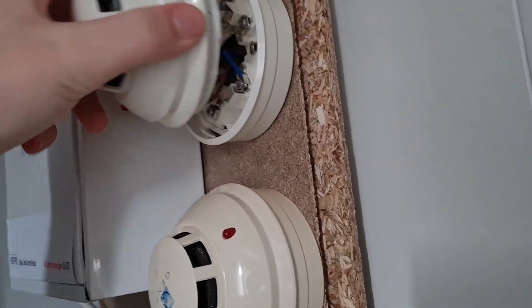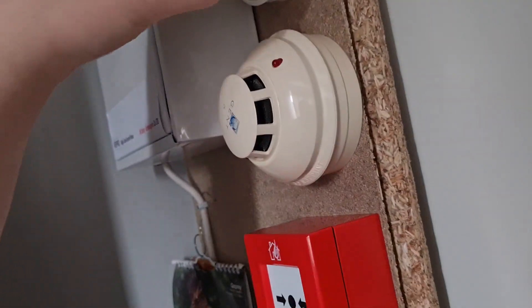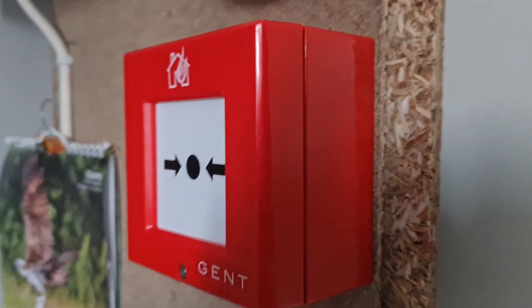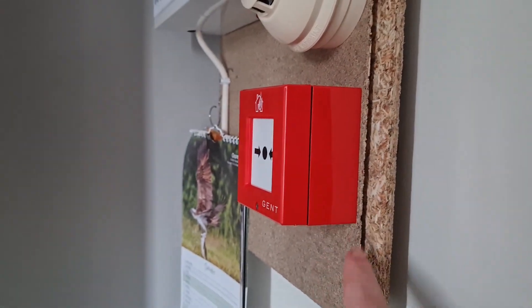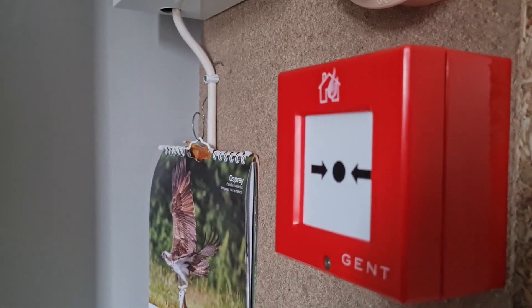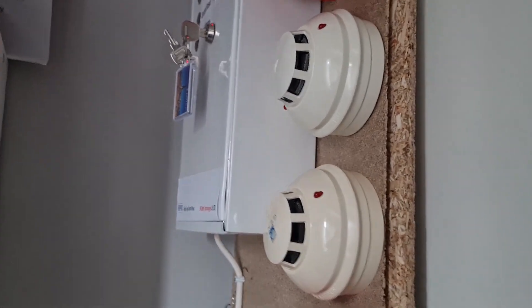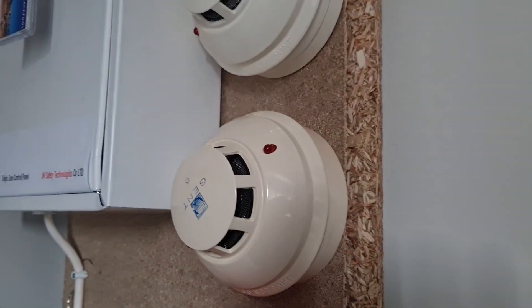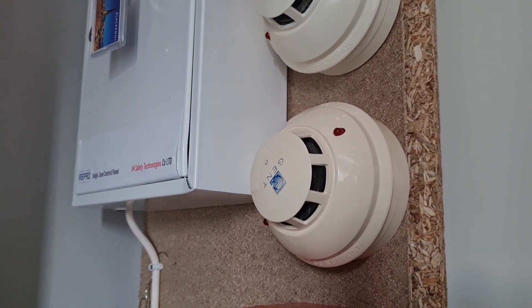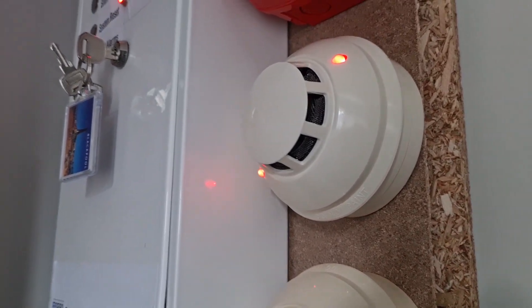These conventional detectors are not new — this one's whiter than the other, though I think it's actually older; this one was 2007 as far as I'm aware, and the logo one is 2012. Then there's the 1195, a newer model also from 2012 that came new in box — that's its original back box, so it looks very nice. These detectors are really sensitive, so there's a significant chance both will go off at the same time, but I'll try to mitigate that by spraying at an upward angle toward the one with no logo.